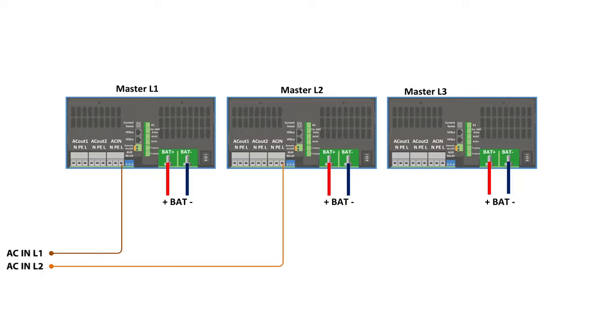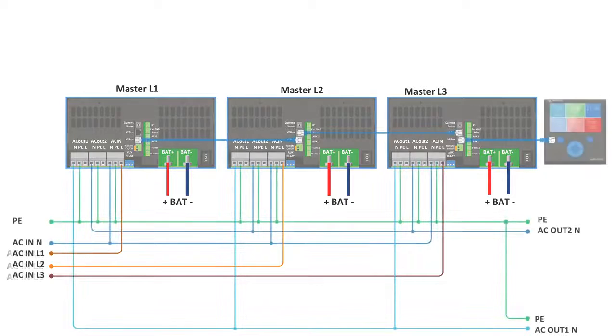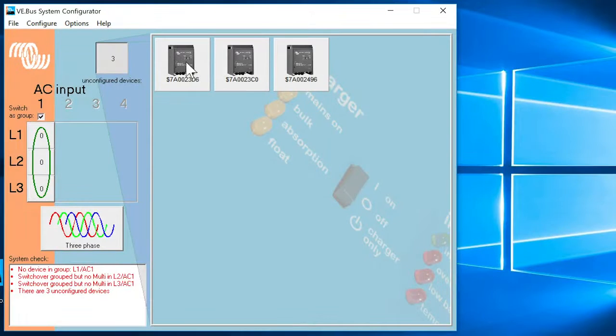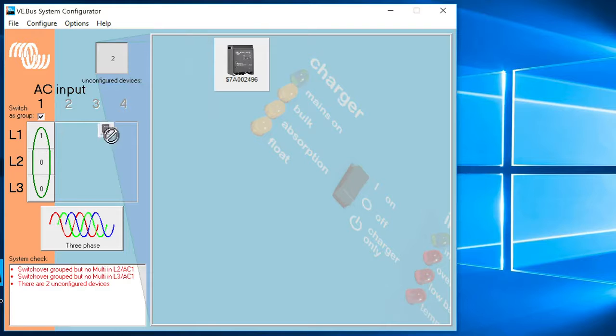Remember to take care of the AC input phase rotations and have them match to each of the units. So phase 1 matches the phase 1 programmed unit, and so on. If possible, configure the systems so the AC input phases match the order on the wall. However, if the units are wired up with an incorrect phase rotation, it is possible to correct this in software. We've now made all the physical connections we need to do with the MultiPlus-IIs. We're going to go through some of the commissioning process steps.